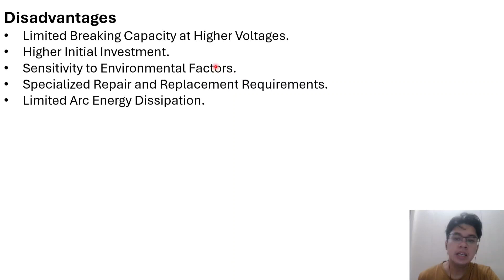Another disadvantage is its higher initial cost compared to some other types of circuit breakers. Vacuum circuit breakers can also be sensitive to certain environmental conditions that may affect their external components and operating mechanisms. In addition, repair and replacement may require specialized equipment and trained personnel because the vacuum interrupter is sealed. So it is not easy to maintain. Another limitation is that vacuum has limited arc energy dissipation capability during extremely high fault conditions.